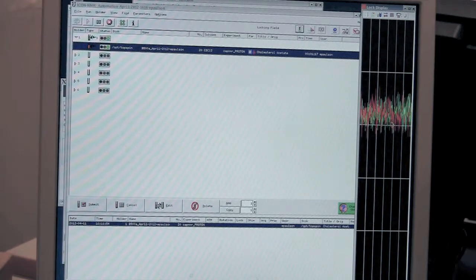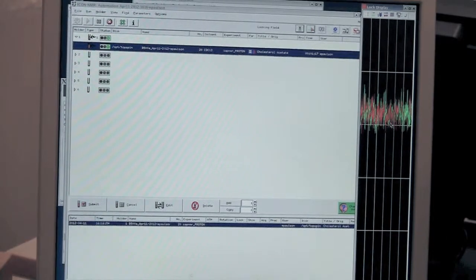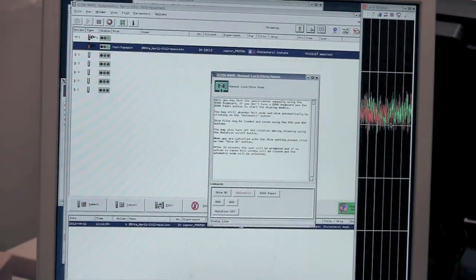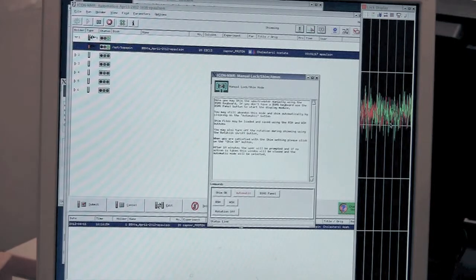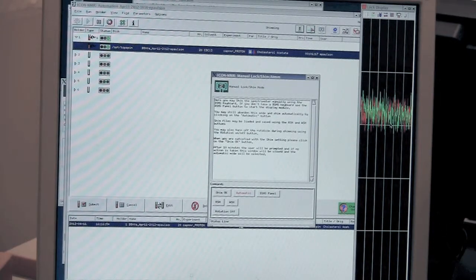Okay, now for shimming, I'm not going to cover that right now, but shimming on the capillary NMR probe is very different than it is on a normal NMR probe, because the capillary is oriented perpendicular to the field, whereas a normal NMR tube is parallel to the field. So the main shims that you would use would be y, z squared, x squared minus y squared, xy, and to a lesser degree x and z. So shimming with your normal z and z squared will not improve the shims.